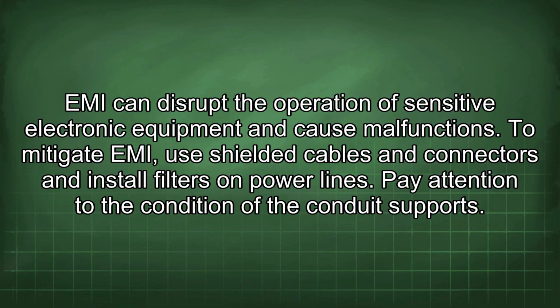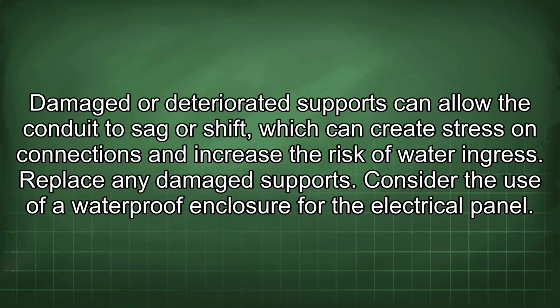Pay attention to the condition of the conduit supports. Damaged or deteriorated supports can allow the conduit to sag or shift, which can create stress on connections and increase the risk of water ingress. Replace any damaged supports. Consider the use of a waterproof enclosure for the electrical panel.